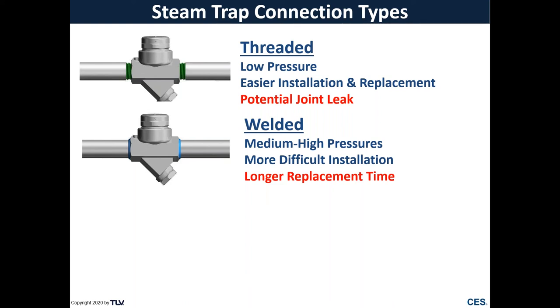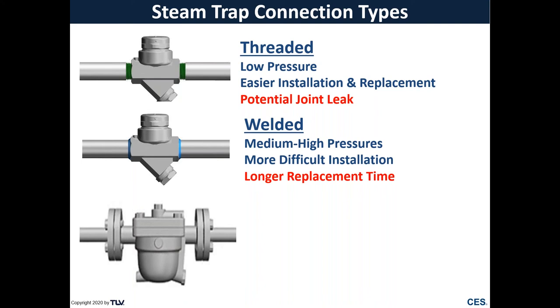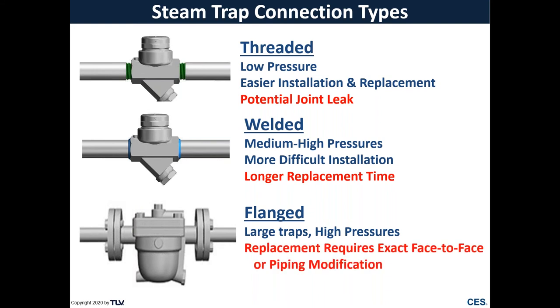Another common type of connection is your flanged connection. These you generally see on larger steam traps and at higher pressures. But replacement of this often requires either an exact face-to-face or piping modifications, which can be a bit difficult.